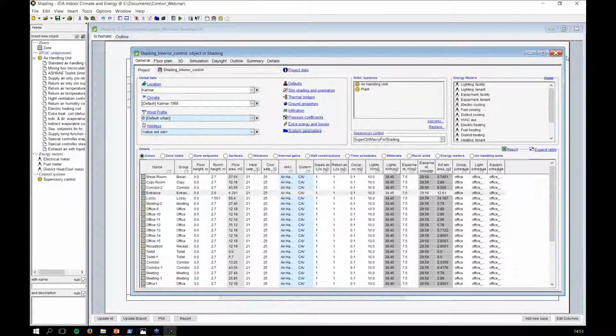Okay, so that is my base case. What about the other child cases? What I did was I kept everything the same. We're still working with the same model here, with the same window model, but I changed one thing. In the supervisory control, for this proportional controller, when you open it, you have a couple of parameters. It allows you to set the maximum and minimum of the signal that you would like to control. So when I say I want to control my daylight to be within 2000 and 2100 lux, that's what's being translated here between high and low.